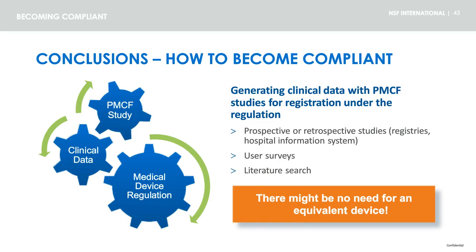If you have previously used clinical data from an equivalent device which no longer fulfills the regulation requirements of equivalence, or if your device has been on the market for a long time, but there are not enough clinical data available, or for other reasons you have determined that further clinical data is required for the registration of your device under the regulation, you might consider collecting clinical data now, during the transition period, with your current CE marked device by performing a PMCF study. If you have only small gaps on clinical data, you can instead plan and perform other PMCF activities.